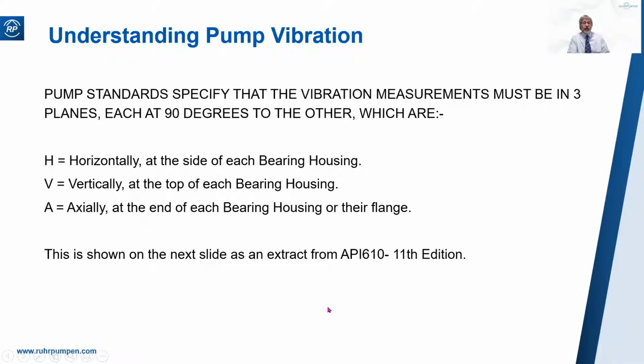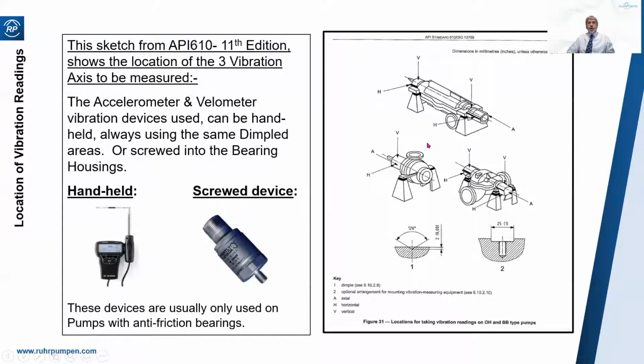Vibration is measured in 3 planes: horizontally, vertically, and axially. And API 610 shows us where we have to measure them. Horizontally, vertically, and axially, there will be dimples on the case to show consistently where you will be measuring. And it can be done 2 ways. It can either be with a handheld meter, which is when you need the dimples, or you could have a permanently installed accelerometer or velometer.